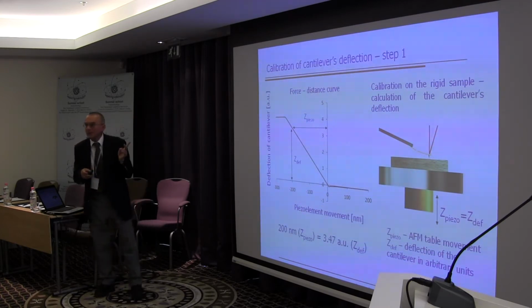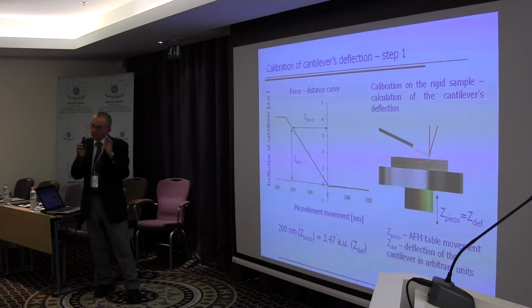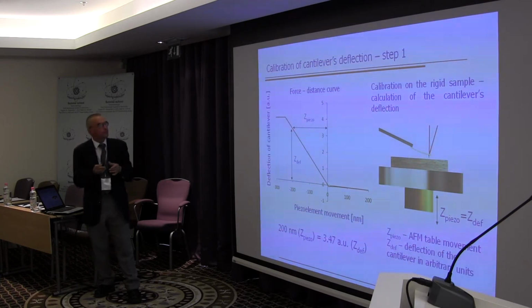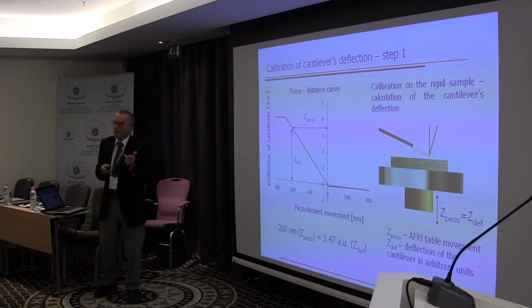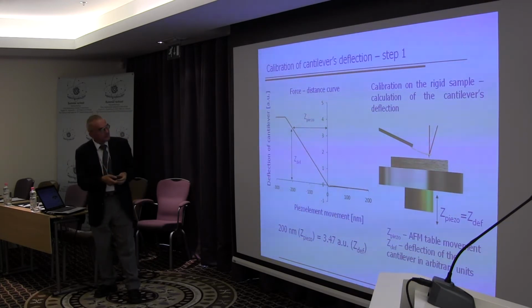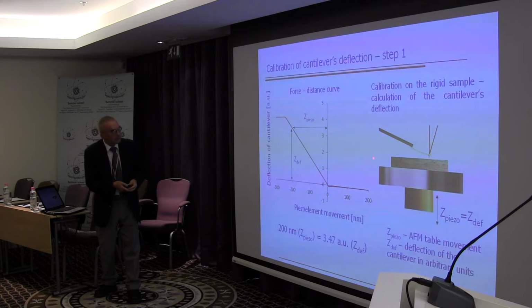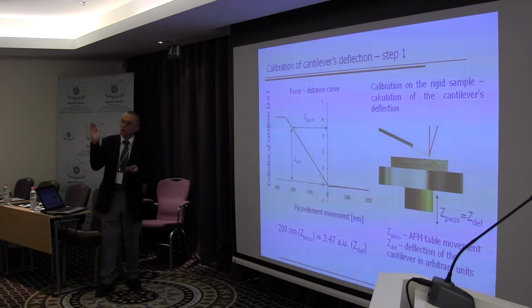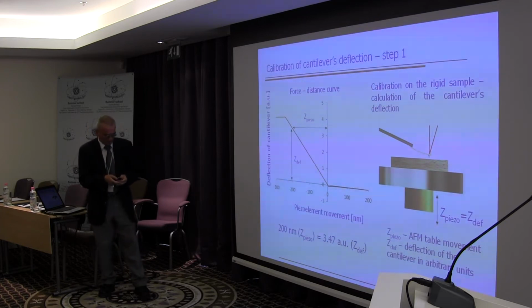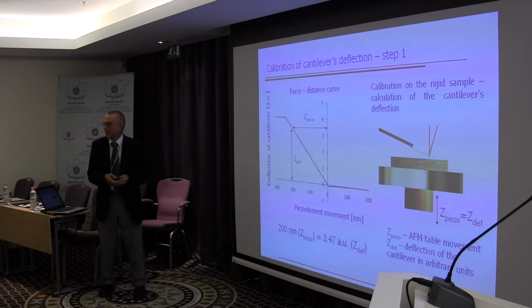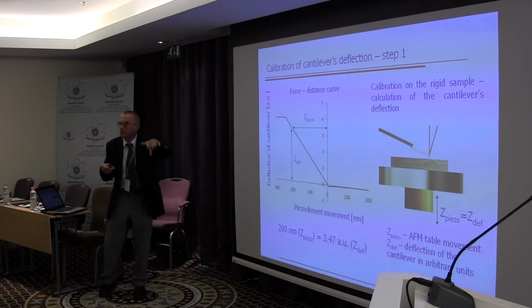And the idea of this calibration is such that if we have such a spring with well-defined stiffness, calibrated exactly in our laboratory somewhere, then after that, if we make first experiments, a force distance curve, you know probably what this is. So we are approaching our tip using the scanner to our sample. So this is the approaching, and this is the indentation after contact of the tip with the material.